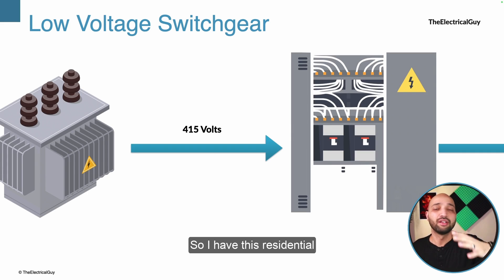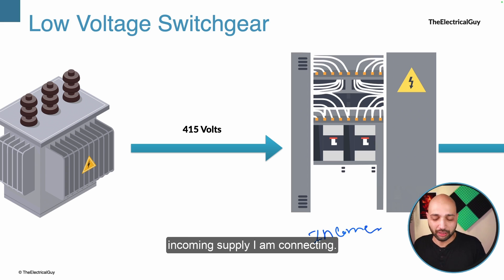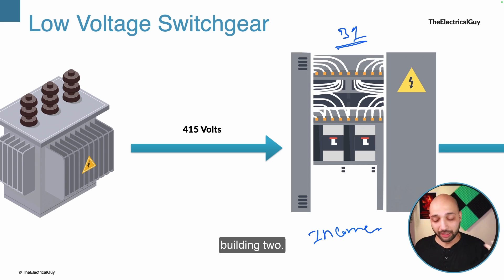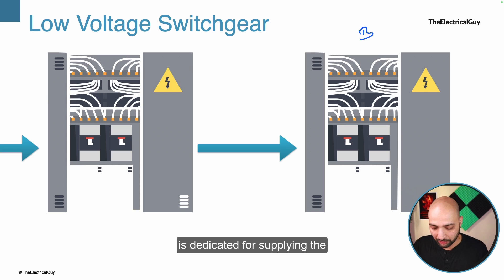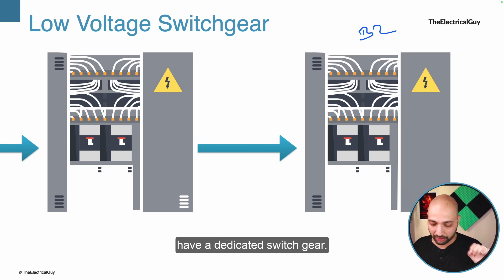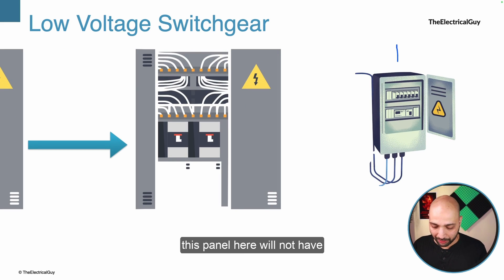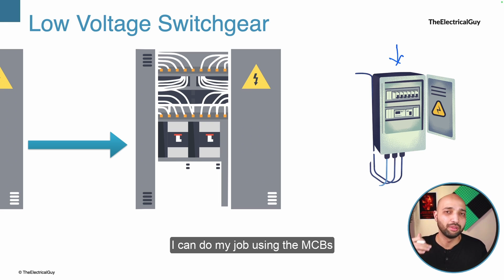In a residential scenario, supply from the utility is connected to the main incomer panel. From there supply goes to building 1. For building 2, a feeder is taken to a dedicated panel. For each floor of the building, a dedicated switchgear is also possible. The floor-level panel does not need an air circuit breaker — the job can be done using MCBs and regular contactors. High rupture capacity air circuit breakers are not required at that level.